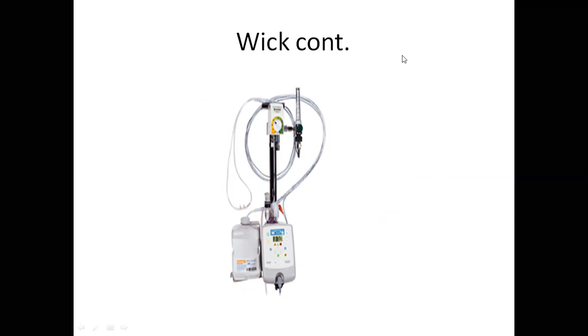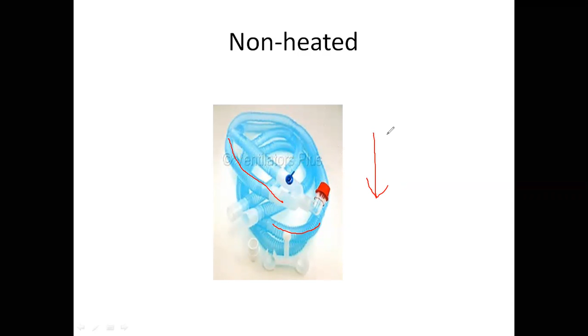And again, not providing commercial for anybody, just showing you what's out there. So we have circuits, and that's a good old 22 millimeter respiratory fitting. And that's what hooks up to either our Passover or our wick humidifiers. Notice this particular circuit is non-heated, it does not have any heater wire flowing up through that circuit. So when that heated humidified gas comes to this circuit, the temperature is lower than the heater. And remember, the colder it is, the less humidity it can hold. So if we have warm humidified gas hitting cold air, it's going to create a cloud almost and condense, and we get rain out. So this tubing is going to fill up with water.